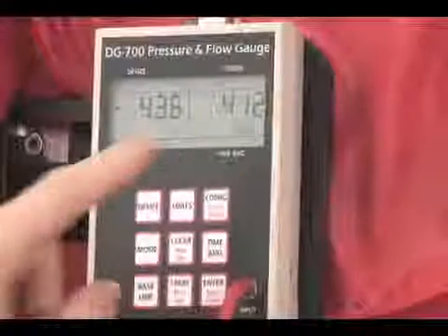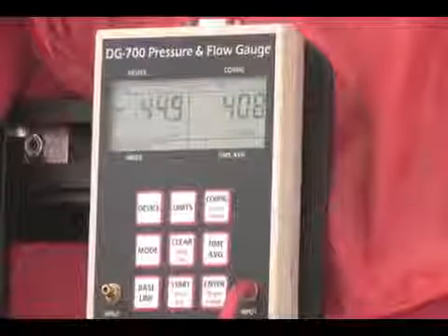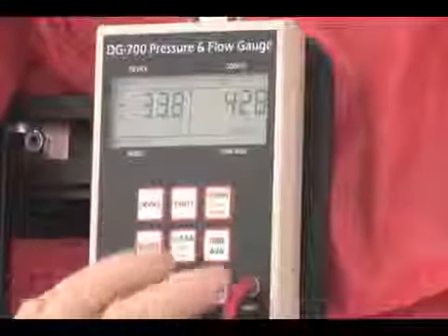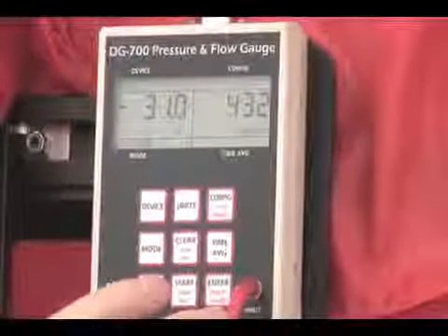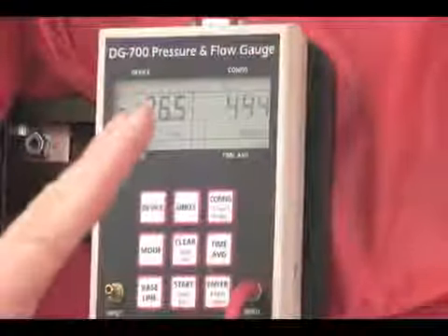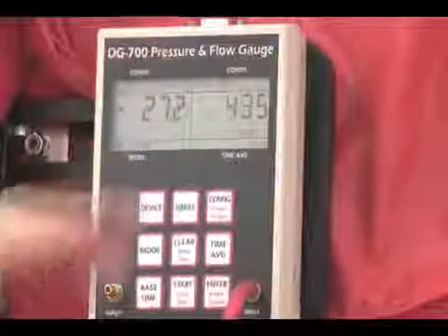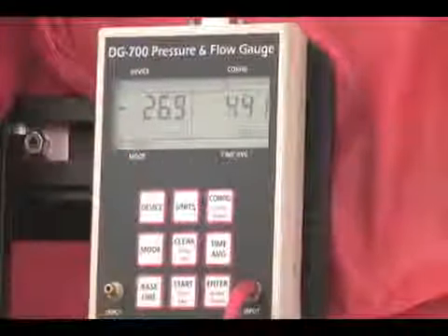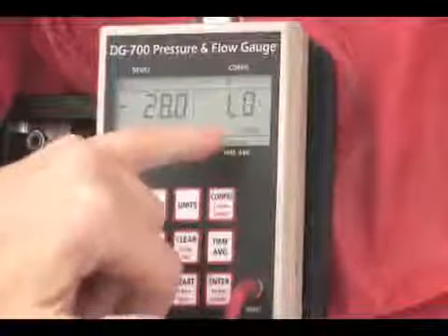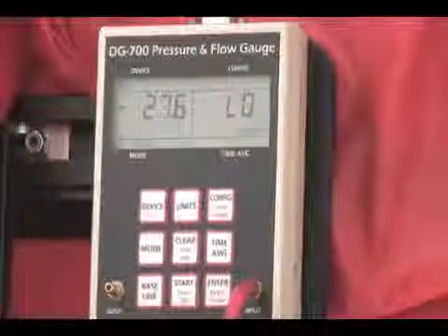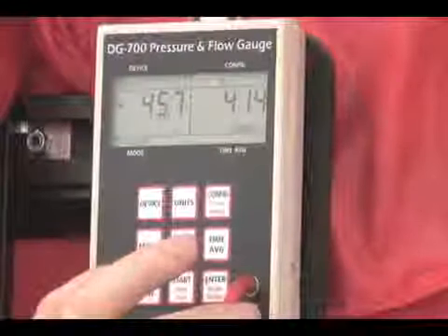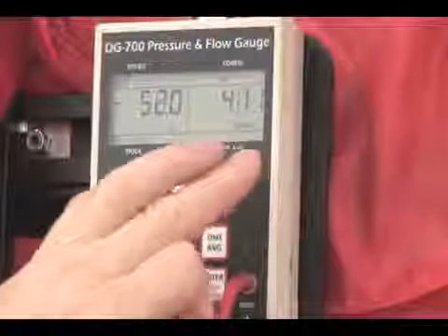It's now 415 CFM. So even if the pressure drops, as we're showing here, you'll notice that the CFM is not dropping very much, because it keeps extrapolating back up to 50 and answering the question mathematically: what would the flow be if I was at 50? So even though we're only at 27, we're still extrapolating back up to 50. The fan is running so slow now that our flow pressure is a little bit low, so let's speed it back up again. Notice again, the flow is not changing very much, because again, it's extrapolating to 50 pascals.